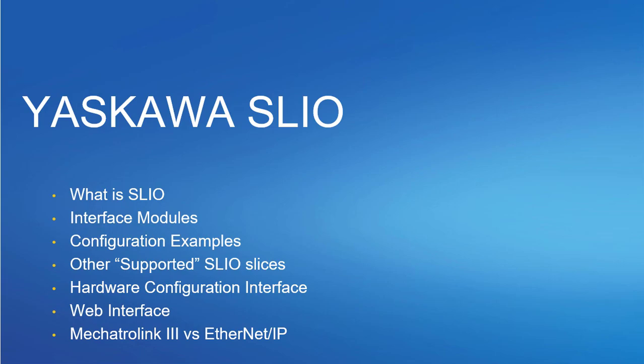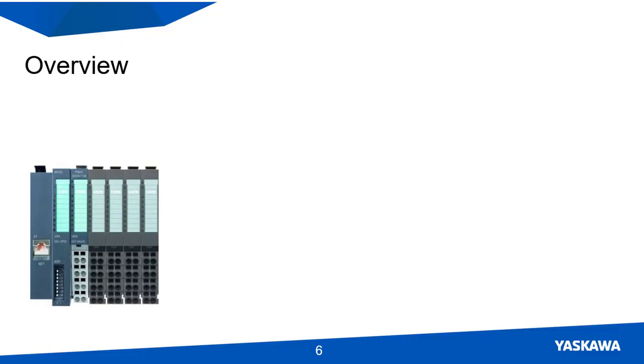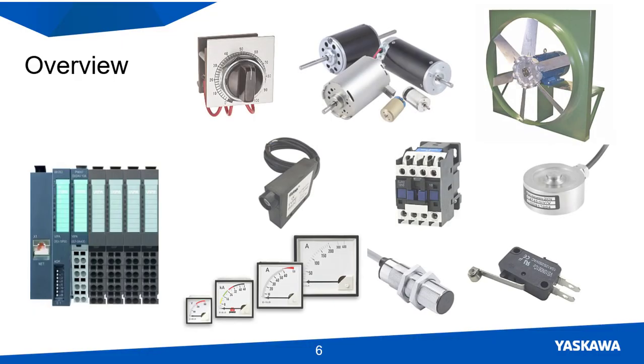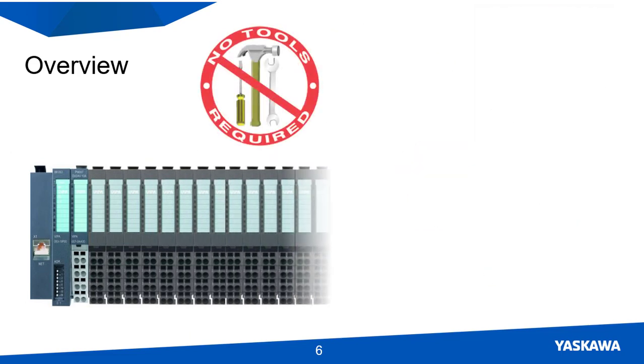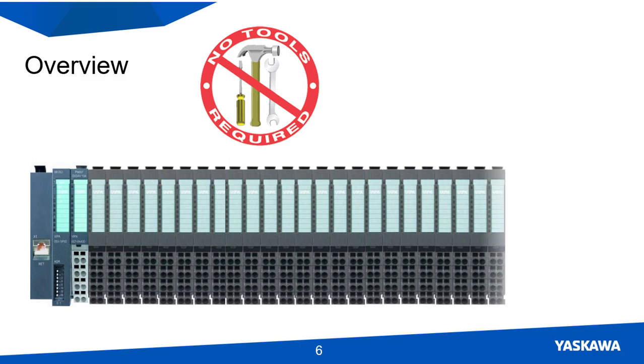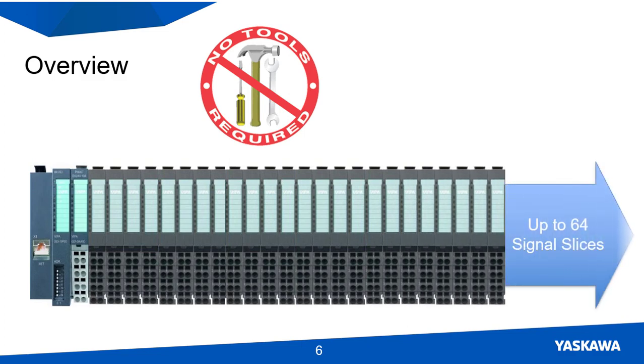Now let's look at this in a little more detail. The SLIO system allows the motion controller to have access to external inputs and outputs. The design is very simple so no tools are needed to install it on the DIN-rail mount. Each interface module can support up to 64 signal modules. You can have any number of power distribution and power supply slices.